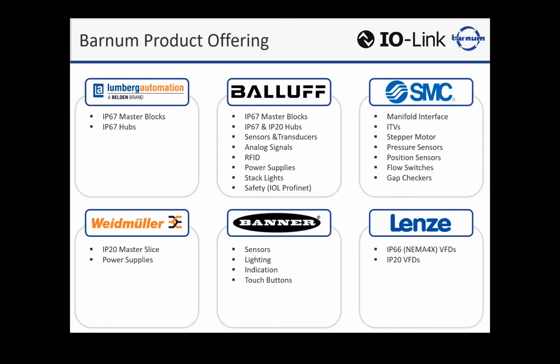Now, when you use IP20 VFDs or motion control, you have everything mounted in the panel. So you're doing a lot of dedicated drops out to your motors, which increases cost, labor, complexity, but not only that, heat and size of your panel. Huge factors. Let's minimize that panel. Let's get as much AC or climate control off that panel as we can. Just one less thing we have to worry about.